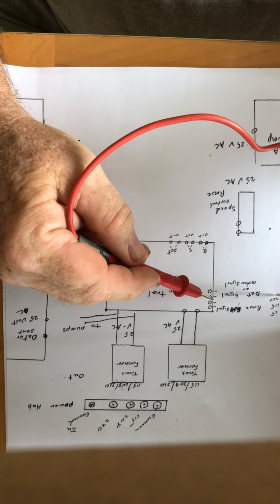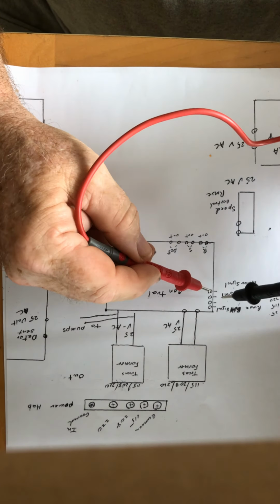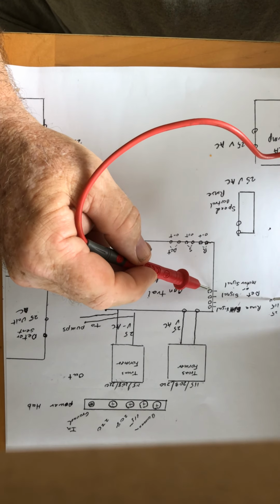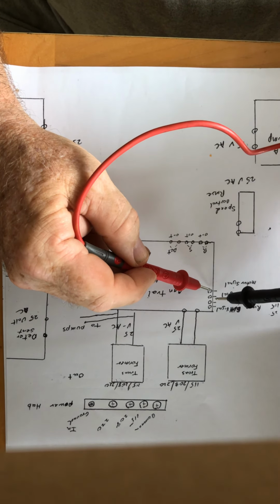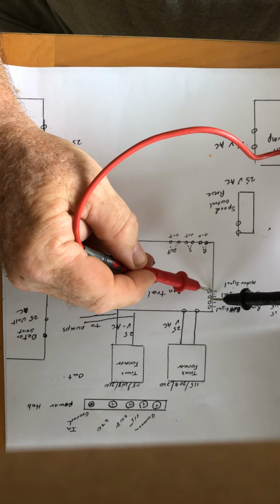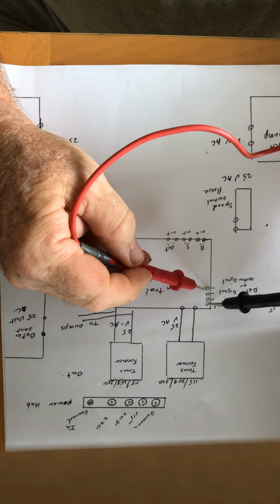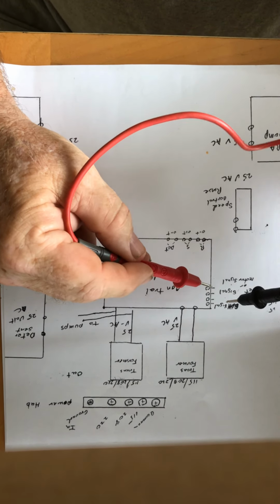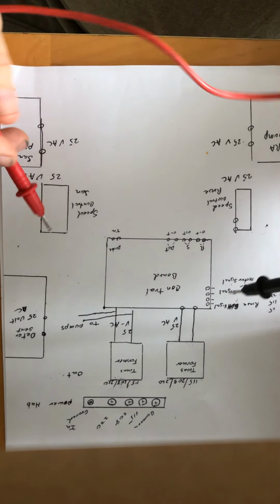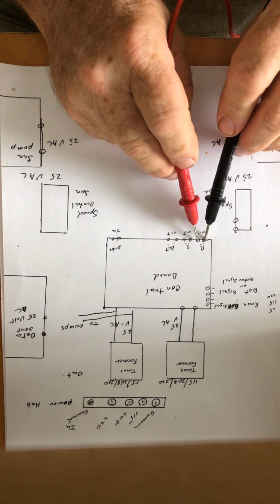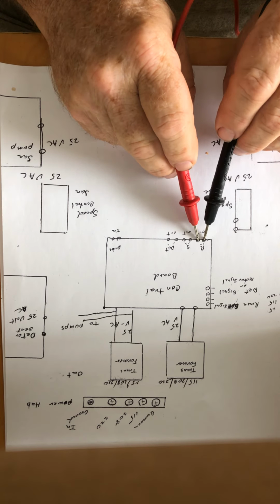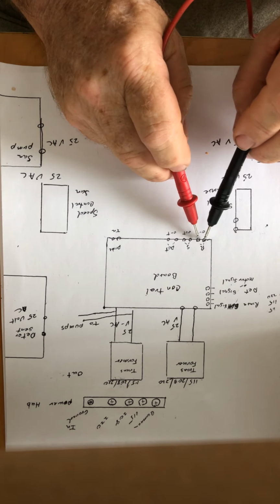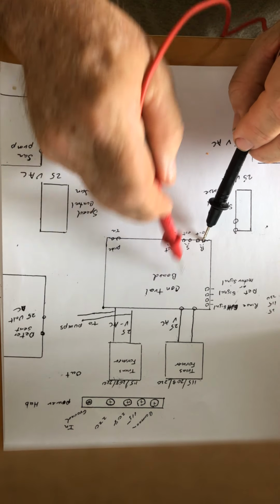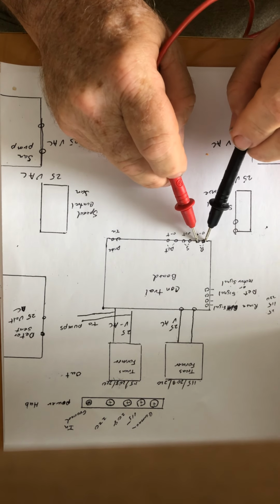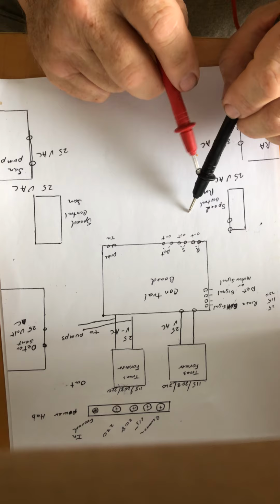Sometimes you have to go to the motor to hook up to 220 to get the detergent, because you want the motor to be running to get a detergent signal. So this could be anything from 220 to 25 volts. It's thin wire, but believe it or not, it only pulls 1 amp, so it's no problem. You can also come out here to see if you have a rinse signal coming out that controls your speed board. You can test it here to see if that's 25 volts.